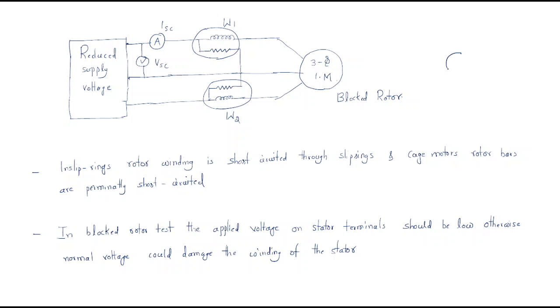In the diagram, the rotor is blocked with a belt. A reduced supply voltage is applied to the three-phase stator. The stator has two watt meters W1 and W2. The stator measurements are the short circuit voltage VSC and current ISC. This is the complete general diagram.